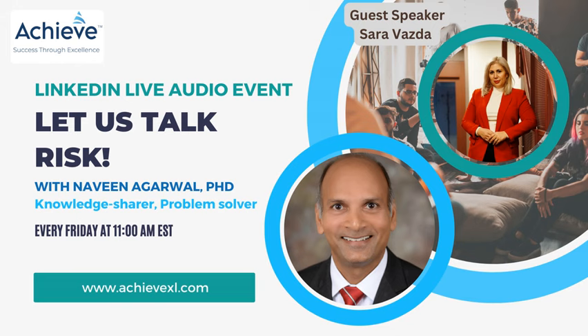Yes, of course. Dr. Naveen, before I do that, there's one thing that I really need to address. It goes back to Lorian's second part when it comes to design validation, equity, patient safety, and different markets. When I look at validation of products, it's important to make sure that you're validating using a representative of the patient population. So it's not only about healthcare professionals, whether in the U.S. market or in Europe. If it's about patient safety, it's about making sure that when you validate your product, you have a representation of patients, not only one certain group.